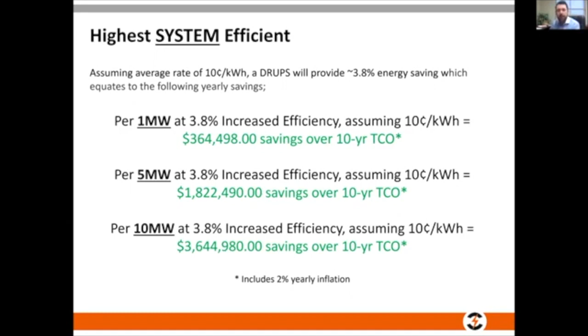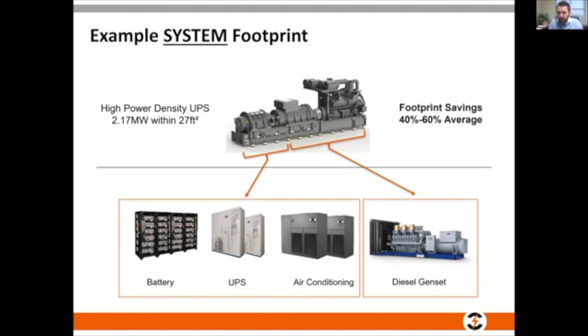By now you'll realize the footprint savings are massive. If you take nothing else away from this, please remember footprint savings are everything for Drups, because whether you go Drups or static, you need a diesel generator. Here's the diesel generator with the two components I've referenced throughout the presentation. What I've added is my flywheel, which is 27 square feet, the size of a table, at 2.2 meg, replacing your rectifier, inverter, static switch, and batteries. And if you consider NFPA 855 in California, you need space between individual battery racks for fire code, which requires even more footprint. So again, huge footprint savings.